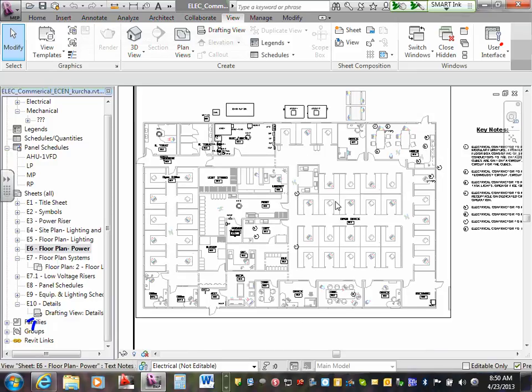But when you have your receptacles, guys, they are going to be located in these areas, in the walls. So what I would do with receptacles is carry them, build a conduit system. We said 9. Probably we can get away with less than 9. You group them and move in the walls. Remember, these walls are open for you to move through. So if I have my receptacles here, all you have to do, if it's in a wall, is go with MC cable from one to another. You're moving like we did in residential, from wall to wall. The studs, I'm telling you guys, are metallic studs, so you move right through from one to another.